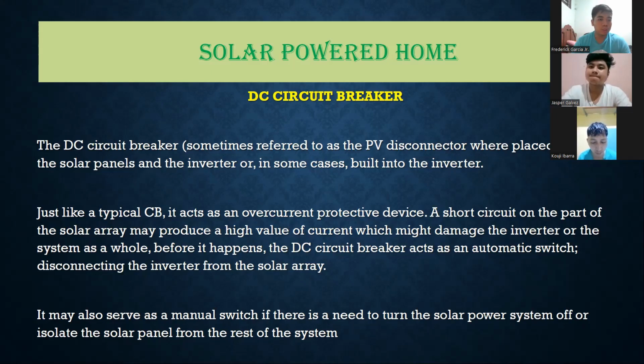So the DC circuit breaker, much like the AC circuit breaker, acts as an overcurrent protection device. In the event of a short circuit, or where the current exceeds the rated capacity, the circuit breaker trips. It is placed after the solar panel but before the AC output of the inverter, somewhere in between, in order to protect either the photovoltaic cells or the inverter itself.